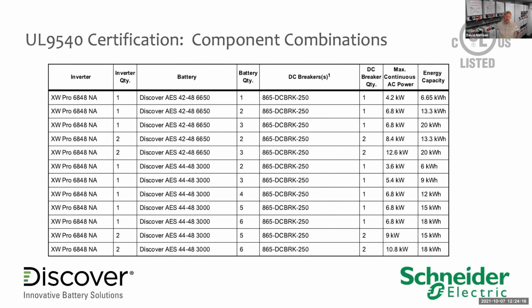Yeah, and that's continuous, right? So depending on what continuous you need for 60 amps, if the 60 amps is a momentary load, you'd probably suffice with less than that. Otherwise, you're basically at that requirement with 2 inverters. Yeah, and if that's just an inductive motor that's starting, then you could probably cover it pretty closely with 1 inverter if it's just a short duration.